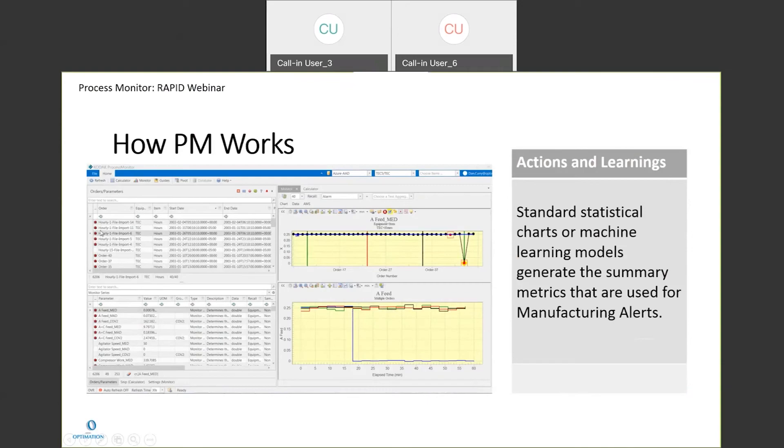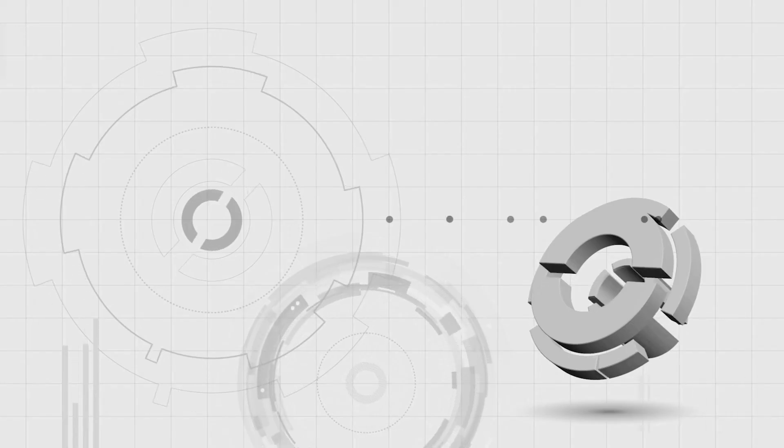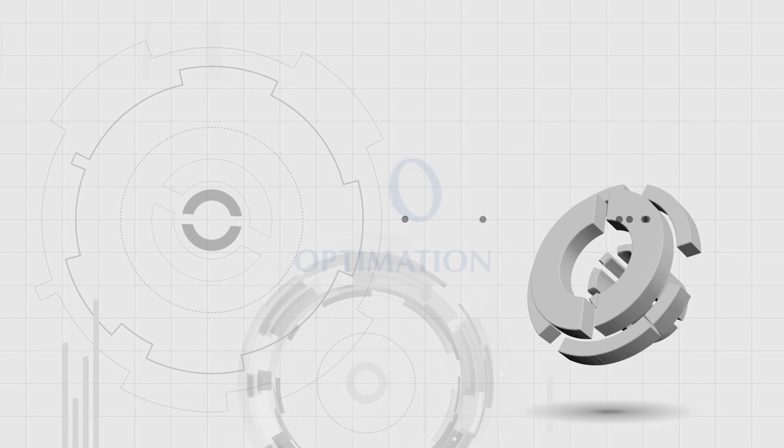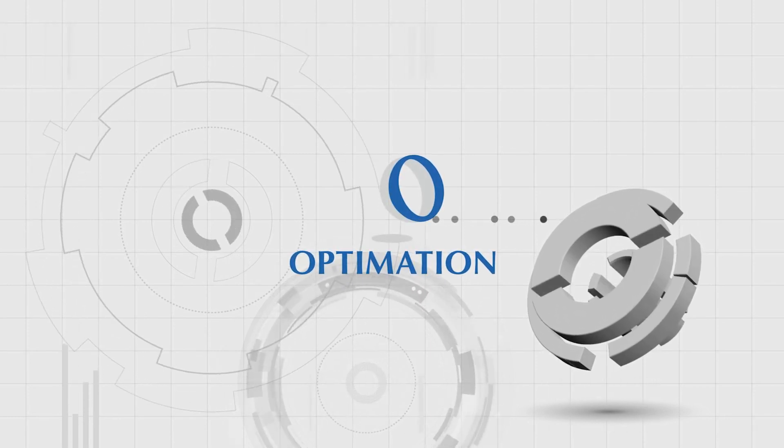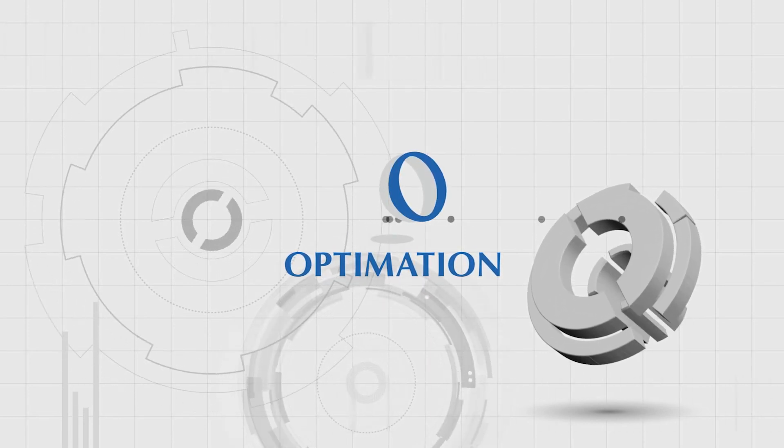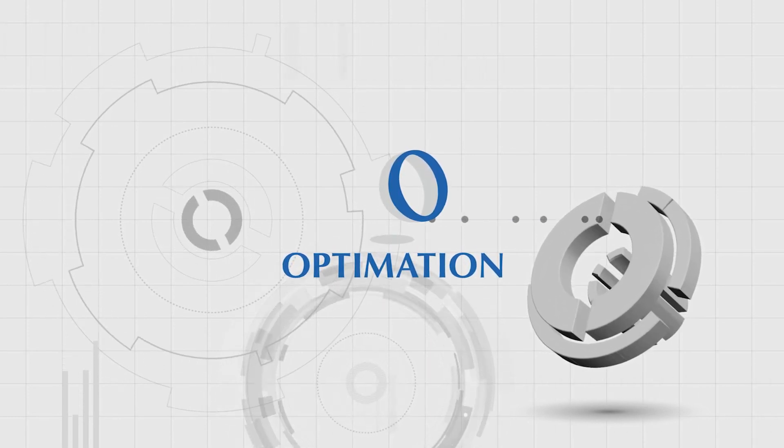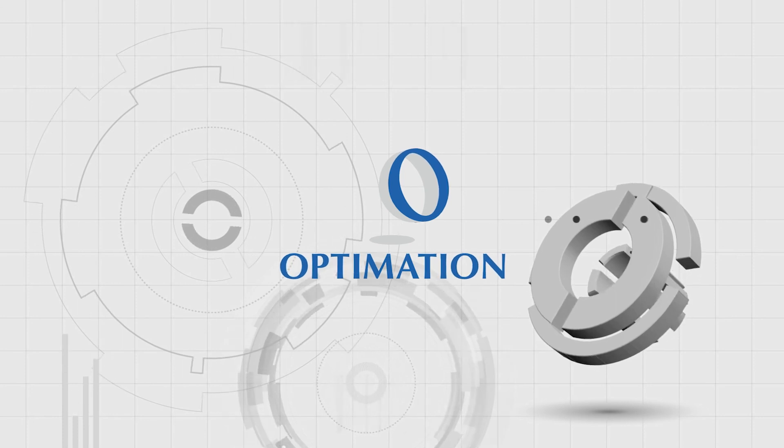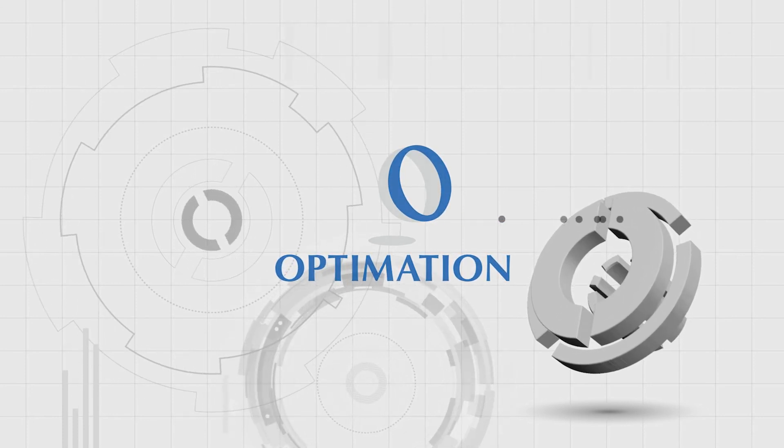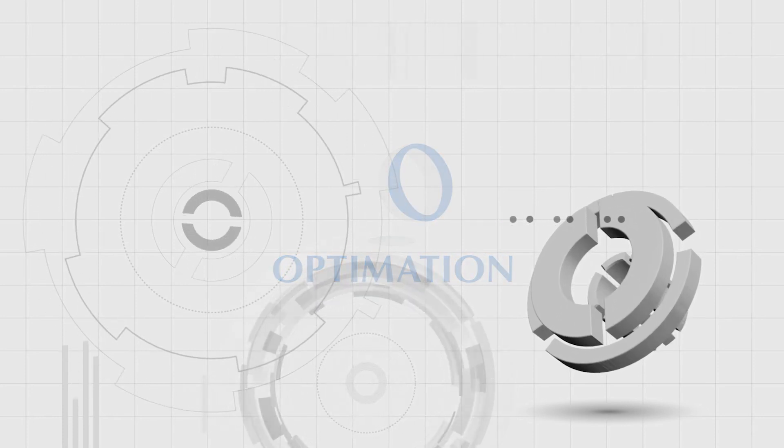So it's just a quick way to show for this batch there's an alarm. And you go over to the parameter here for the median of A feed, and it quickly shows what's abnormal, so you know to go check out basically what's going on with the A feed.